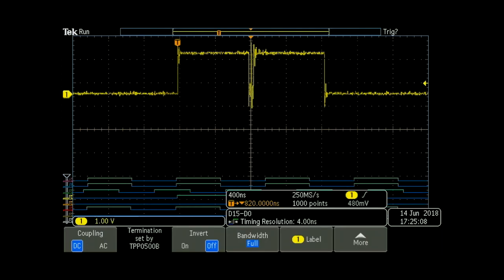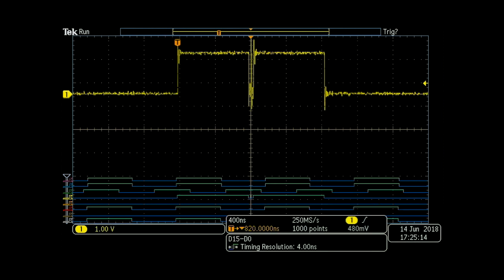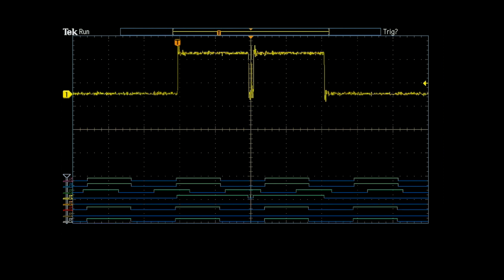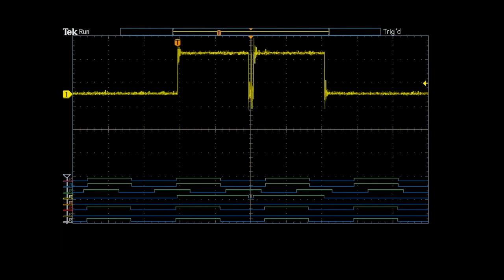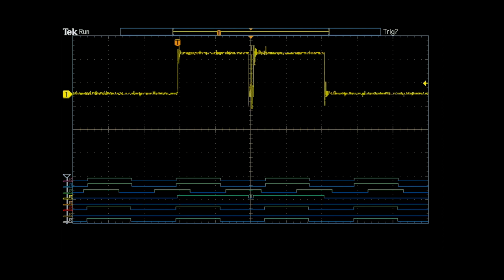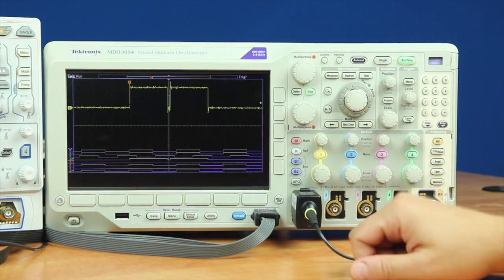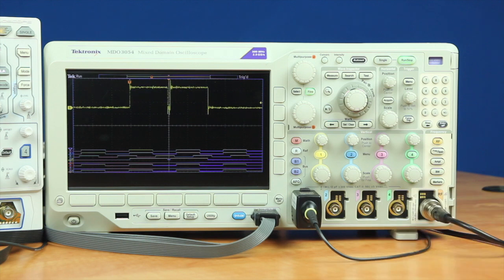To do that we need to switch over to the analog side, where we've turned on channel 1 and some of the digital signals. Now because I've probed the correct spot, we can see the double pulse action on channel 1 and the coordinated activity on the digital channels. The Tektronix MDO 3 does a great job of capturing digital and logic circuits together, but even with the spectrum analyzer built in, you have to move back and forth using the instruments separately.